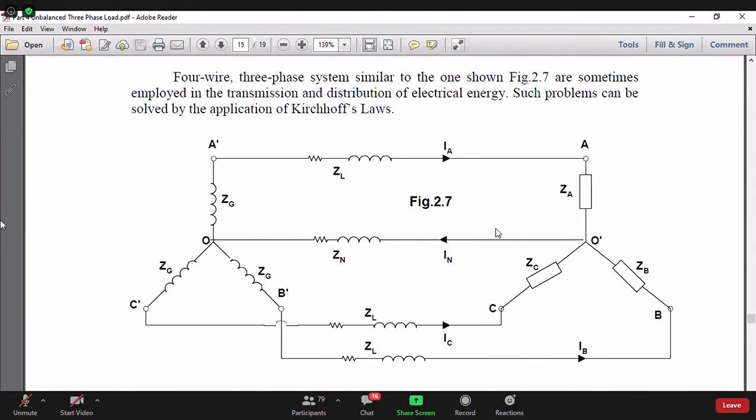You are correct, but there are examples. I can show you in a different way. We are not prepared for it today, but you have a point. To explain that, we need something more. But what we always say is that neutral shift being 0 should be the criterion for identification of unbalance. We don't recommend going by the neutral current, because who has told you that your waveform is sinusoidal? Is there any guarantee? No.